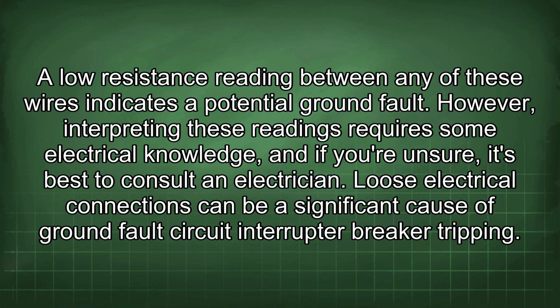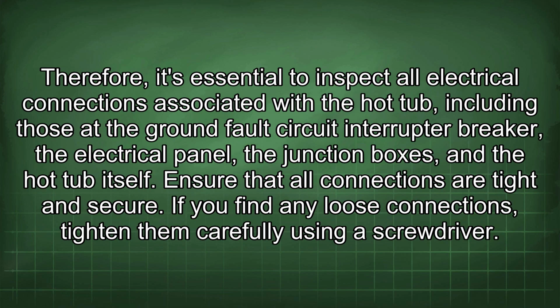Loose electrical connections can be a significant cause of ground fault circuit interrupter breaker tripping. Therefore, it's essential to inspect all electrical connections associated with the hot tub, including those of the ground fault circuit interrupter breaker, the electrical panel, the junction boxes, and the hot tub itself. Ensure that all connections are tight and secure.